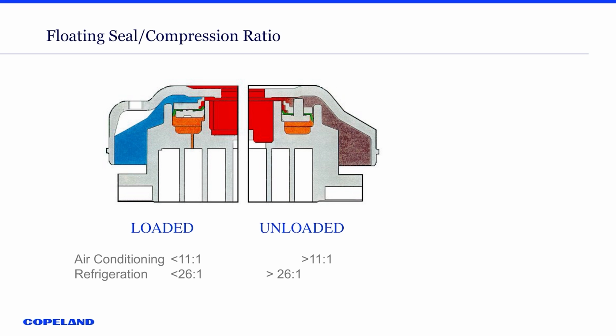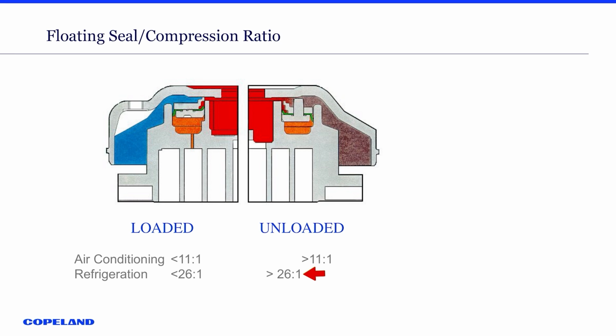So this shows that floating seal. Now, I'll talk about compression ratio in a second here, but once we hit, in air conditioning, for an air conditioning scroll, over 11:1 compression ratio, that floating seal will go off balance, and then we'll not be able to compress with that compressor anymore. And with the refrigeration side, once we hit 26:1, then it's going to go off balance, okay?